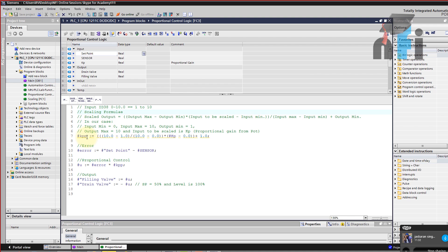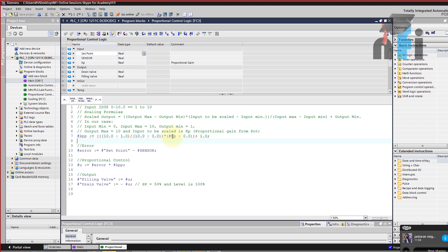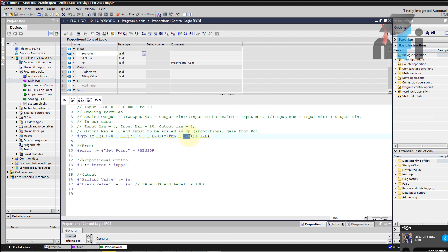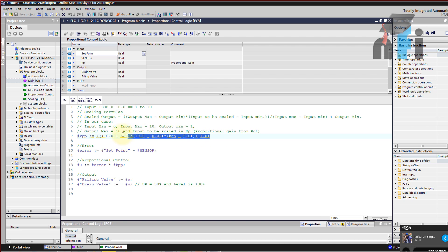In our case, the input to scale was 0 to 10 and the output we needed was 1 to 10, so we have an offset of 1. We took a variable KPP as our scaled output. Output maximum was 10 minus output minimum which was 1, multiplied by the input to be scaled (KP from the potentiometer), minus input minimum (0.0), divided by input maximum (10.0) minus input minimum (0), plus output minimum (1). This scales the range 0–10 to 1–10.